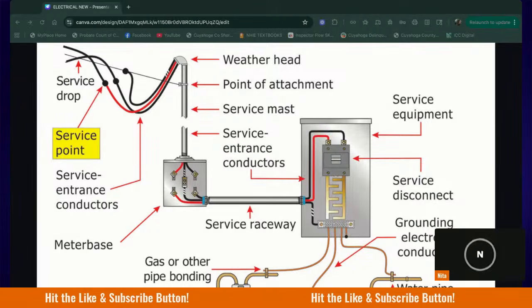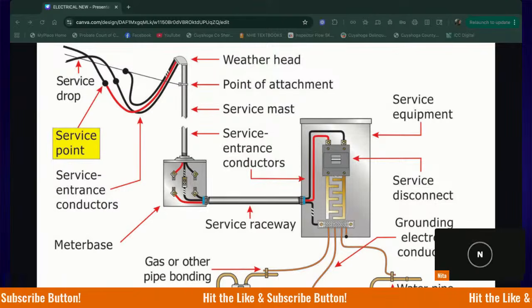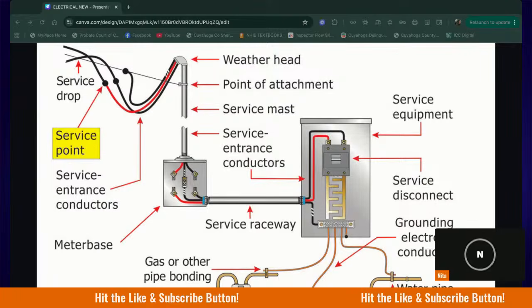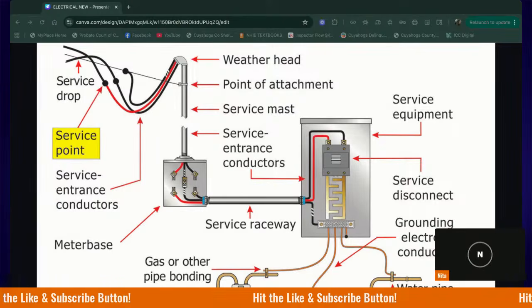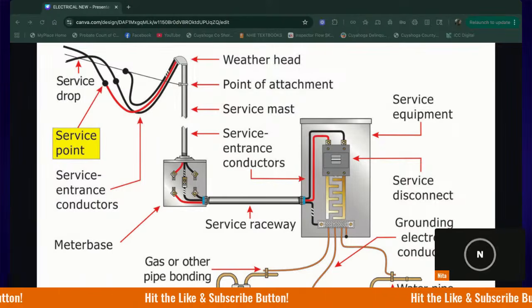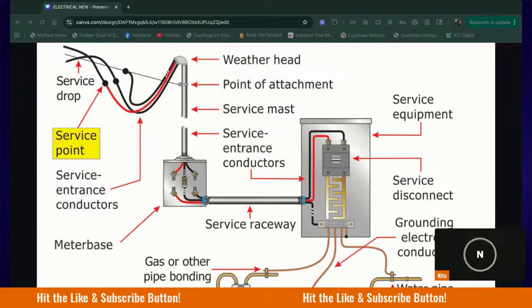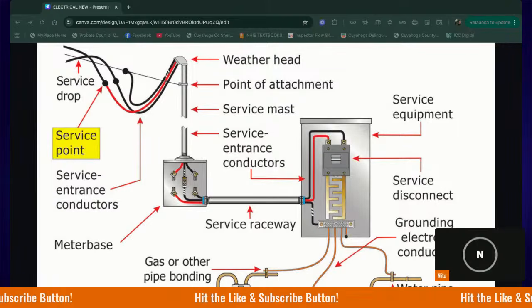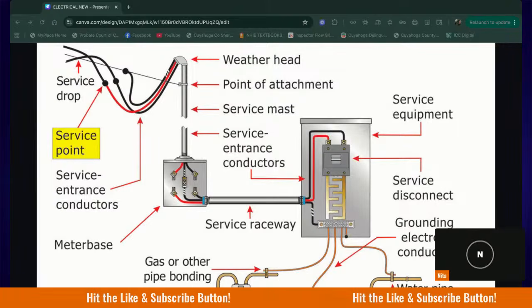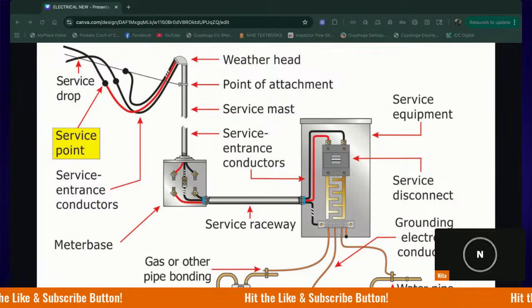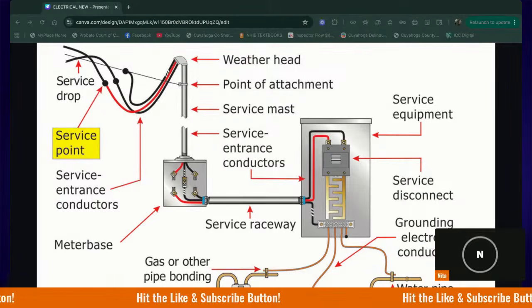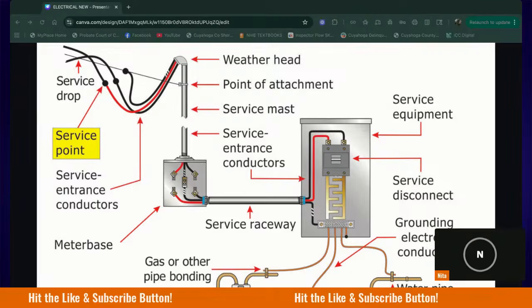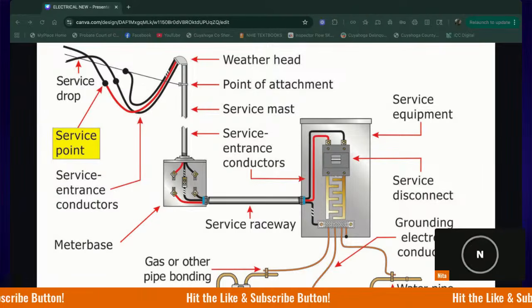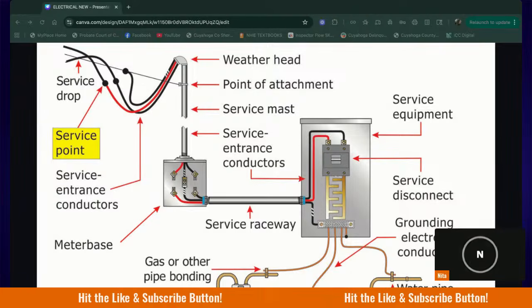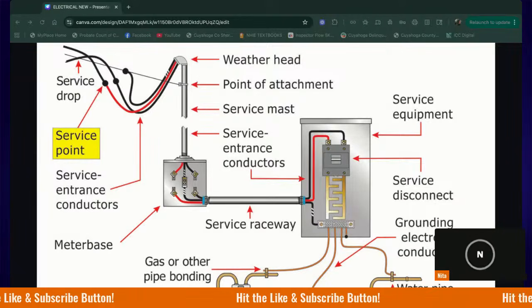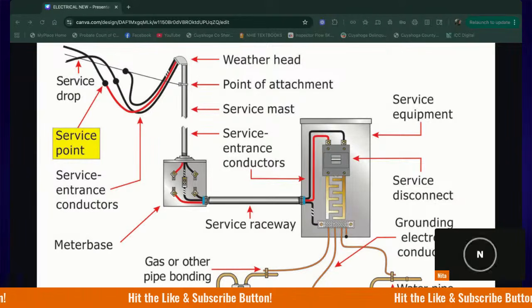And so our service entrance conductors would come into our panel. And then in our panel, they would be connected here to a bus bar, which we'll get into in a second, and the neutral. So now we have our two hots and our neutral that's been brought into the house.